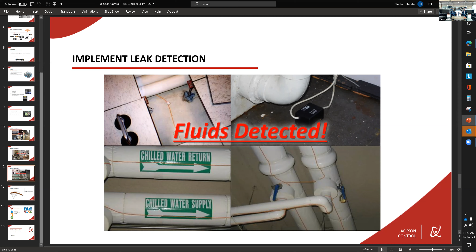So our sensing cable, you may have seen me twirling around this thing, but this is our sensing cable. It's our patented leak detection cable. And if you notice, the two conductive wires that come out of there is what's sensing water coming across that. We have a variety of cables as well. There's a chemical sensing cable. There's a rodent resistant cable, believe it or not, and then a zero halogen cable. So there's 4 total different cables that help to identify these issues and problems.